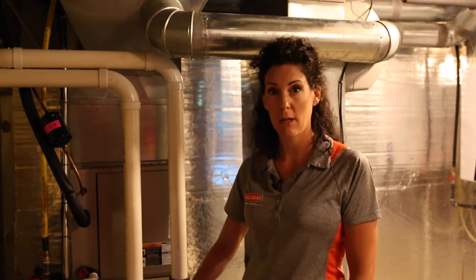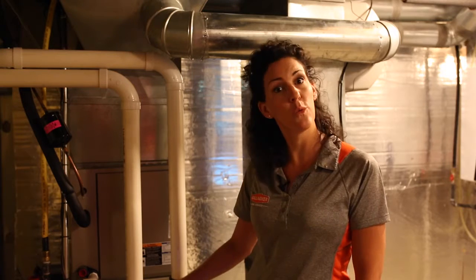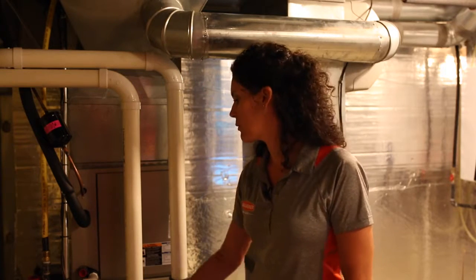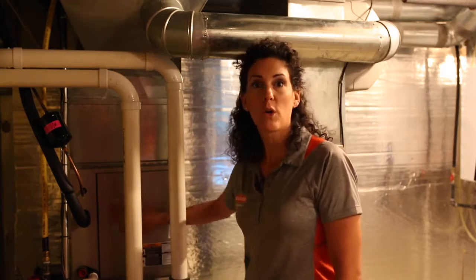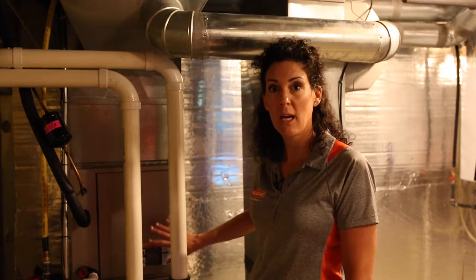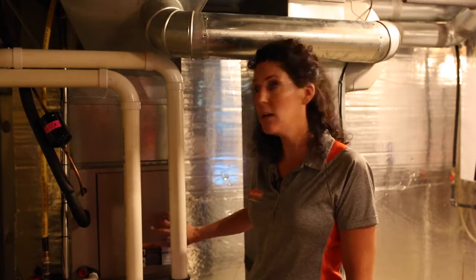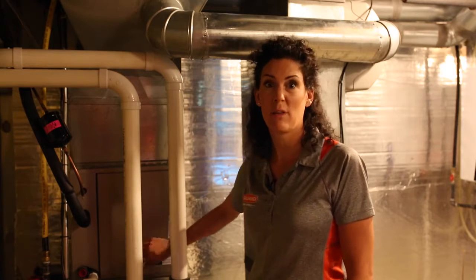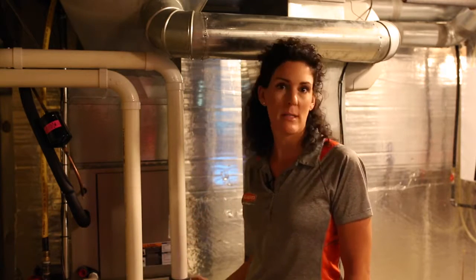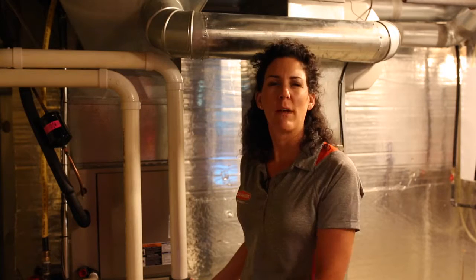Some service examples I can give you as the service manager for our business are, again, the blower motor having to work hard. If that overheats and fails, that's an expensive repair, and that can happen. We've seen it happen quite a bit. Another problem that can occur is in cooling season, when the air is moving through here, it's moving up over your coil, your cooling coil. If it's not getting enough air over that coil, it can freeze this coil. And what happens then, you get water buildup, goes down into your unit, you can get some electrical issues within it.